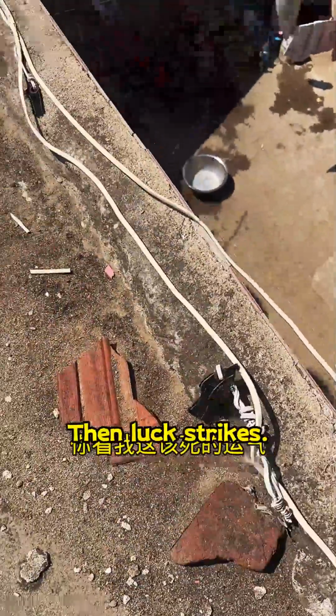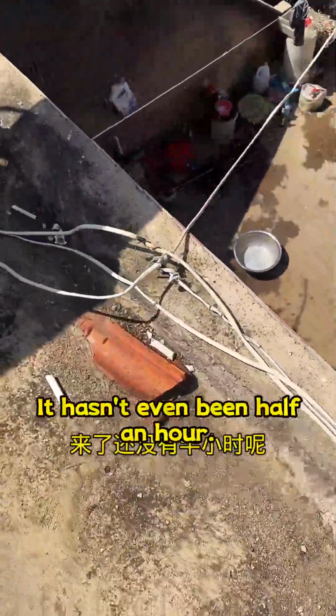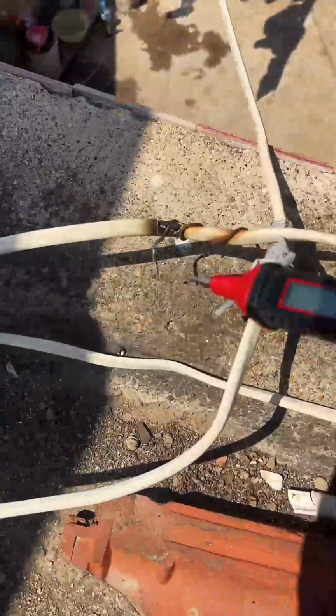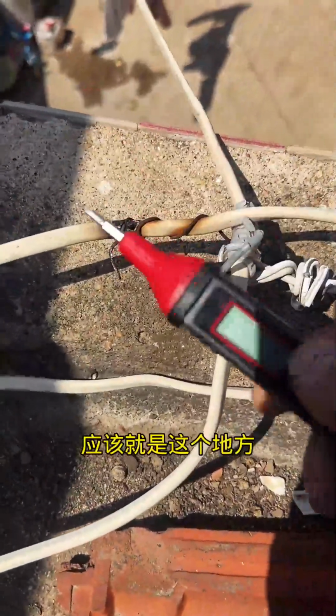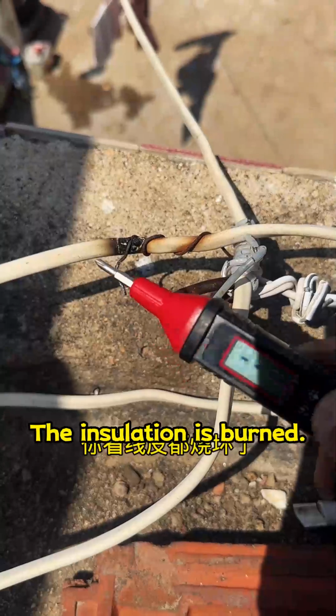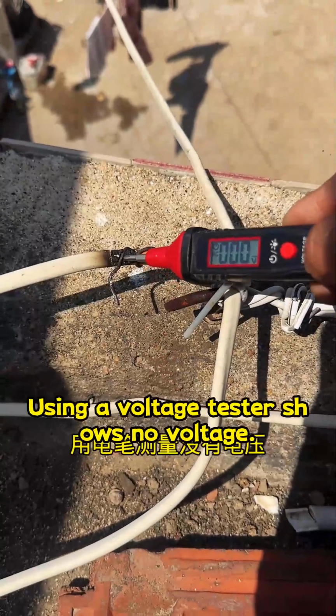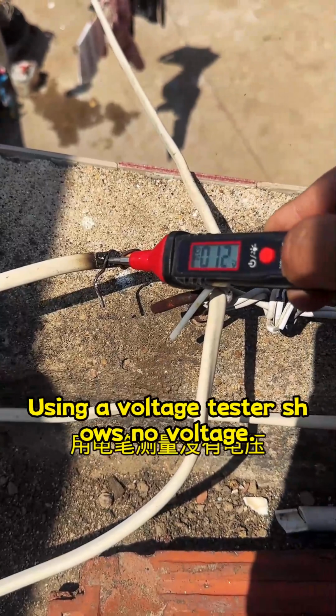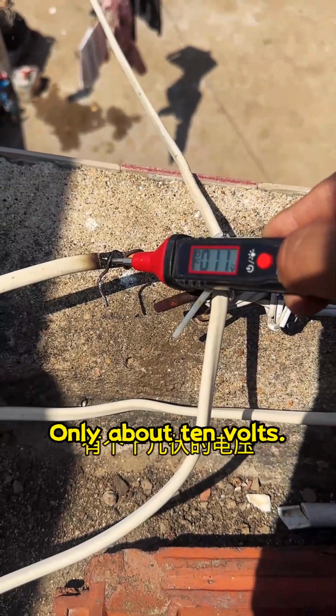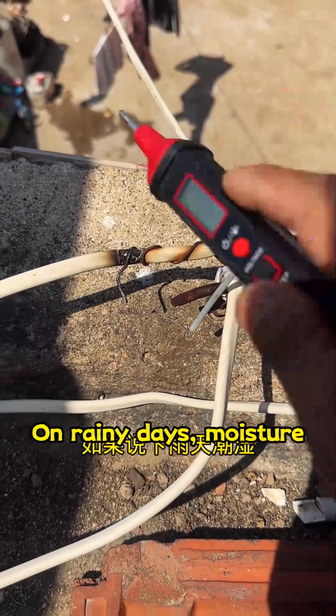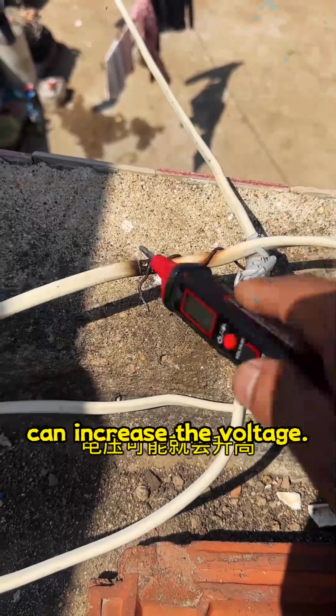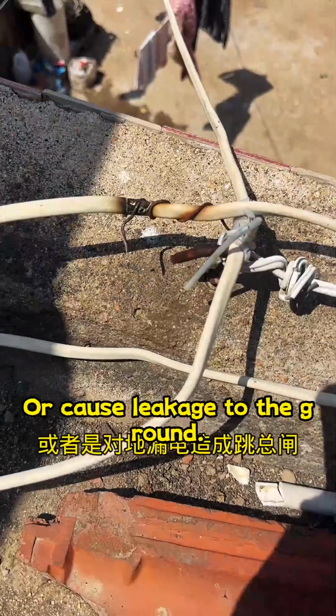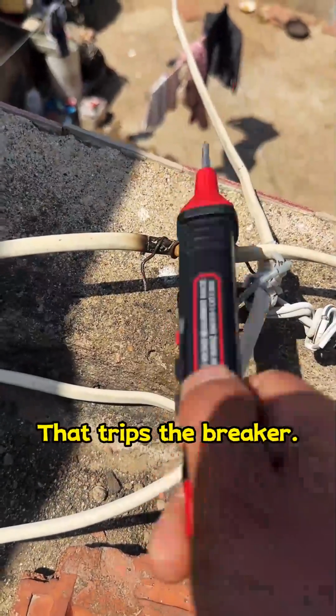Then luck strikes. It hasn't even been half an hour. It must be this spot. The insulation is burned. Using a voltage tester shows no voltage. Only about 10 volts. On rainy days, moisture can increase the voltage or cause leakage to the ground. That trips the breaker.